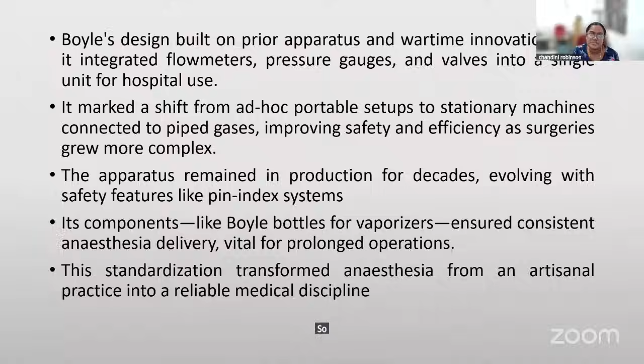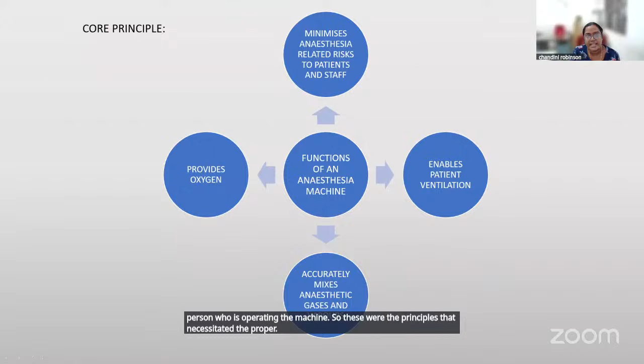Then many of those components were introduced, innovated, and refined to ensure consistent anesthesia delivery, which was vital for prolonged operations. So this enabled standardization, and anesthesia became a more reliable medical discipline, improving upon an artisanal practice. So what are our core expectations from a basic anesthesia machine? We expect it to provide oxygen. We expect it to enable patient ventilation. We expect it to accurately mix the anesthetic gases and vapors and ensure minimum anesthesia-related risk to the patient and to the person operating the machine. So these were the principles that necessitated the proper design of an anesthesia machine.